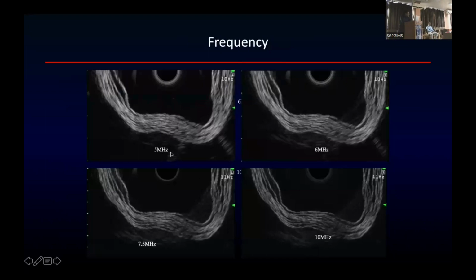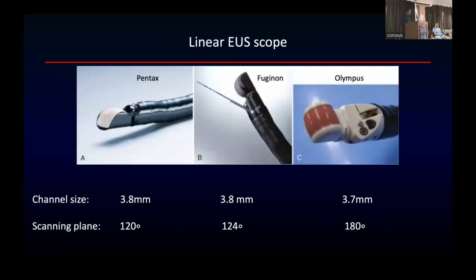So what I mean when I say the frequency ranges from 5 to 10, if you see the bowel wall, the lower the frequency, the lower the resolution. If you have a higher frequency, the depth of the evaluation decreases. However, the resolution of the particular lesion improves. So if you want to image a structure very deep and you use a high frequency, it's not going to serve the purpose. When you have a lesion in the wall where you want better resolution, then you can use a higher frequency to evaluate the lesion.